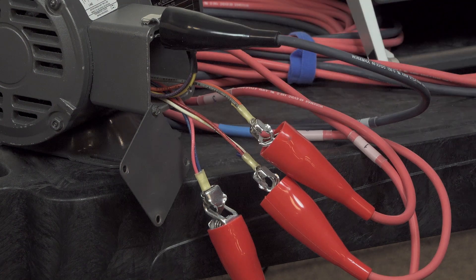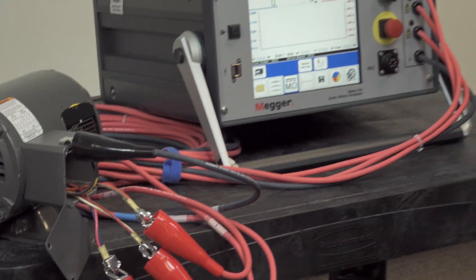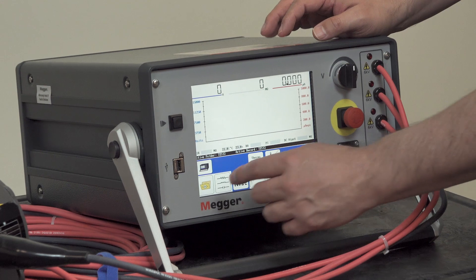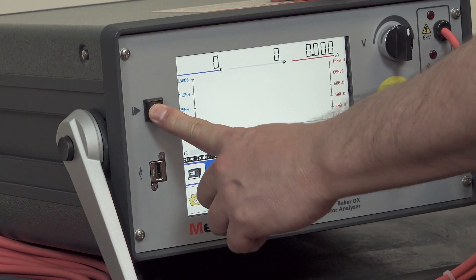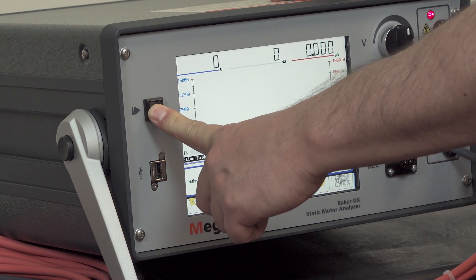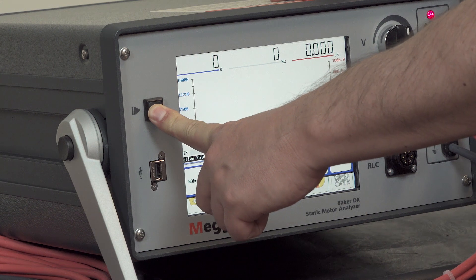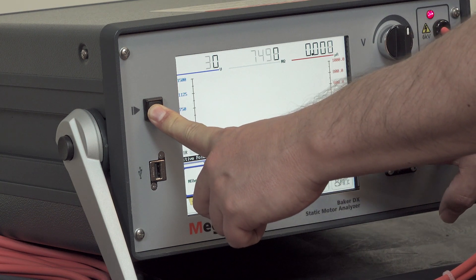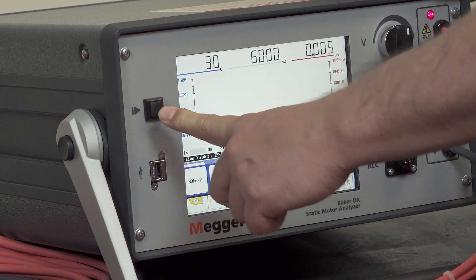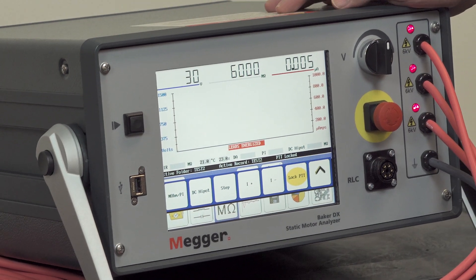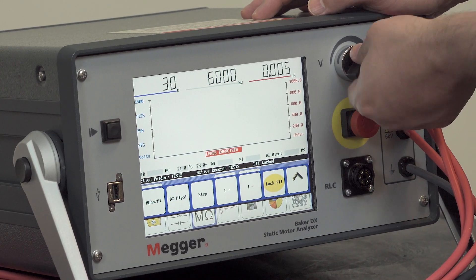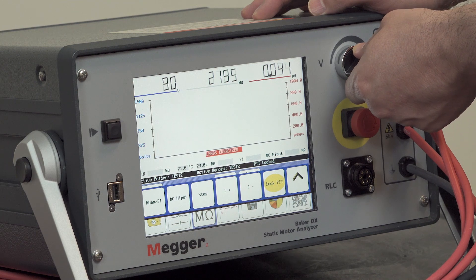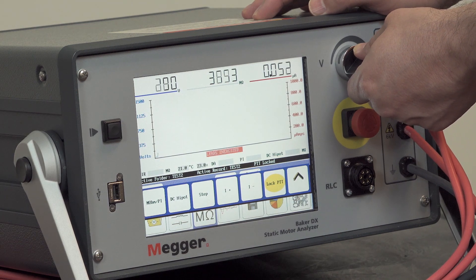We're ready to commence our testing, so we're going to momentarily press the push to test button, and then we're going to press the lock push to test button and release the push to test button. And now we'll raise the voltage to the desired test voltage. In this case, the 460 volt motor, we'll test at 500 volts.